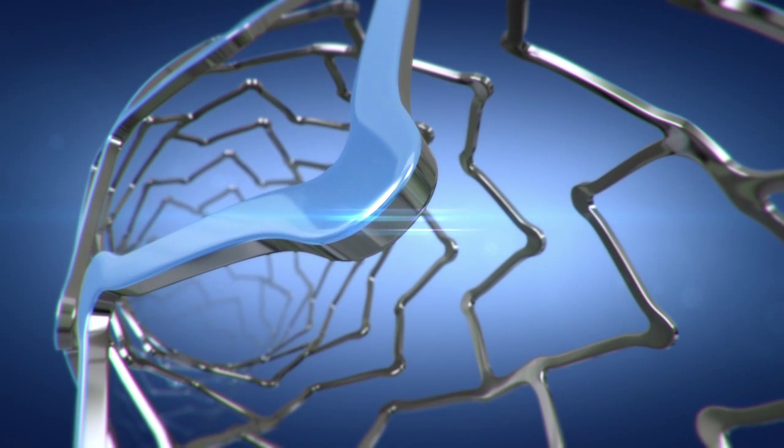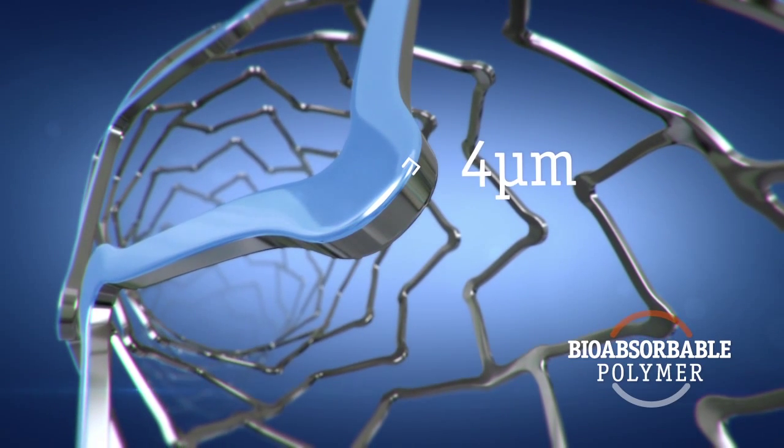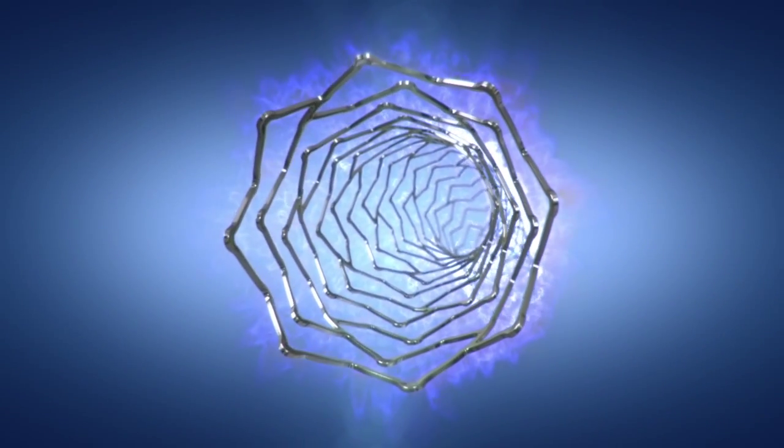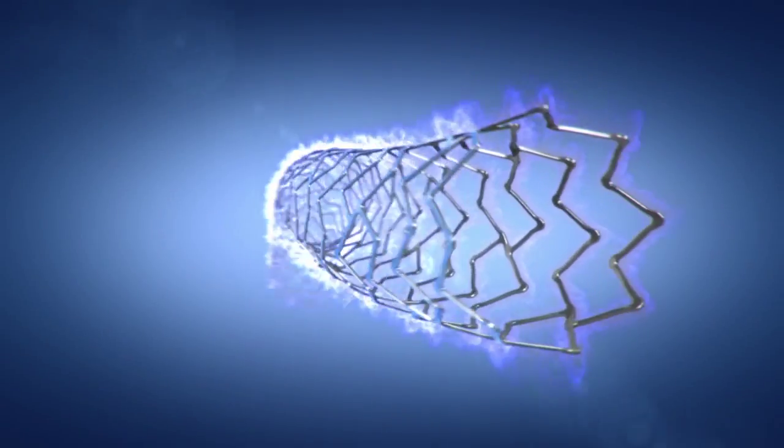This coating consists of a bioabsorbable polymer that is 4 microns thick and is coupled with the market leading Everolimus drug, allowing for synchronous drug and polymer absorption.